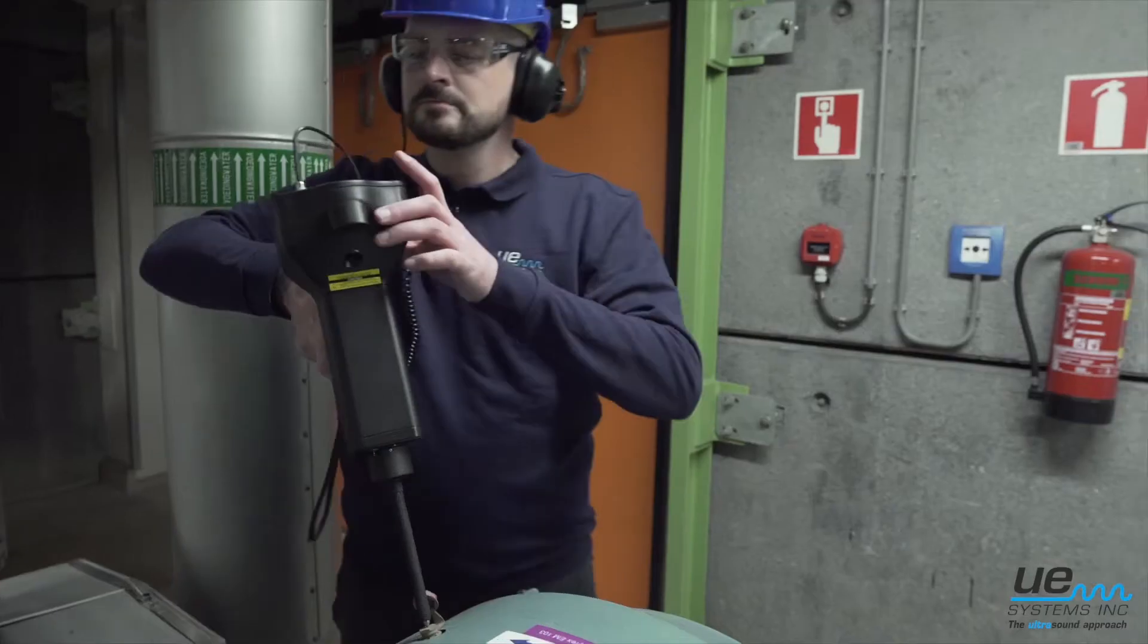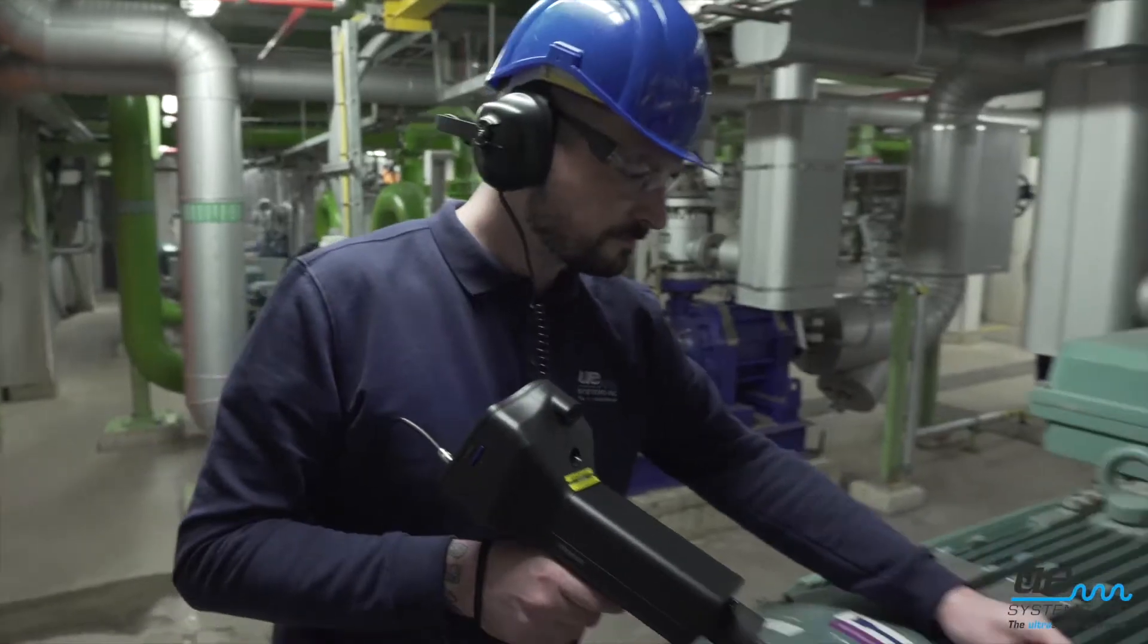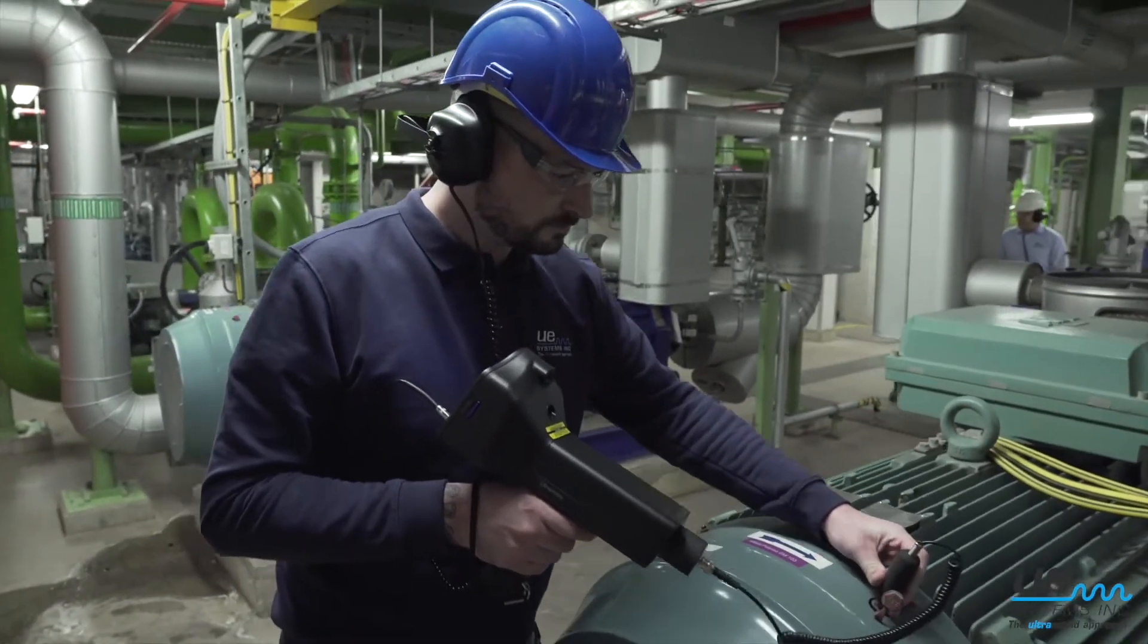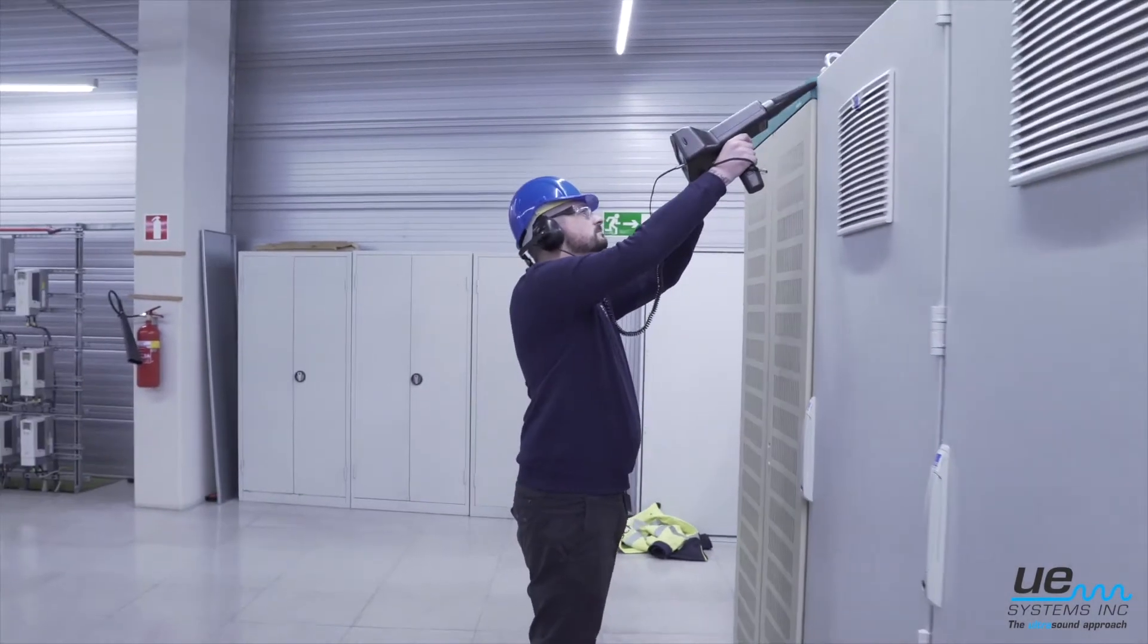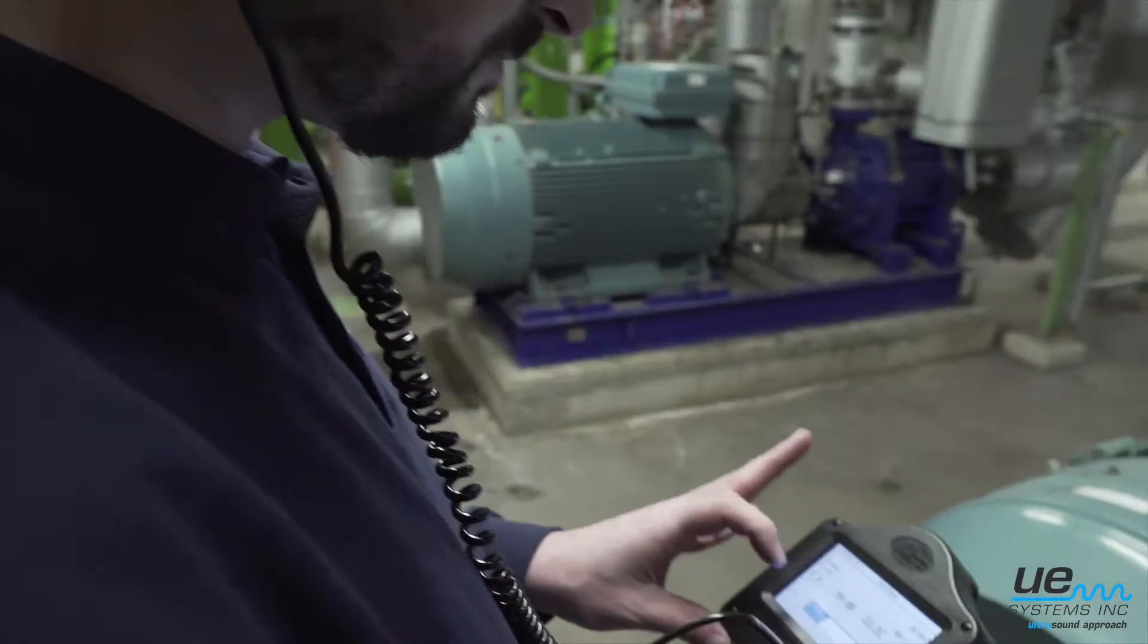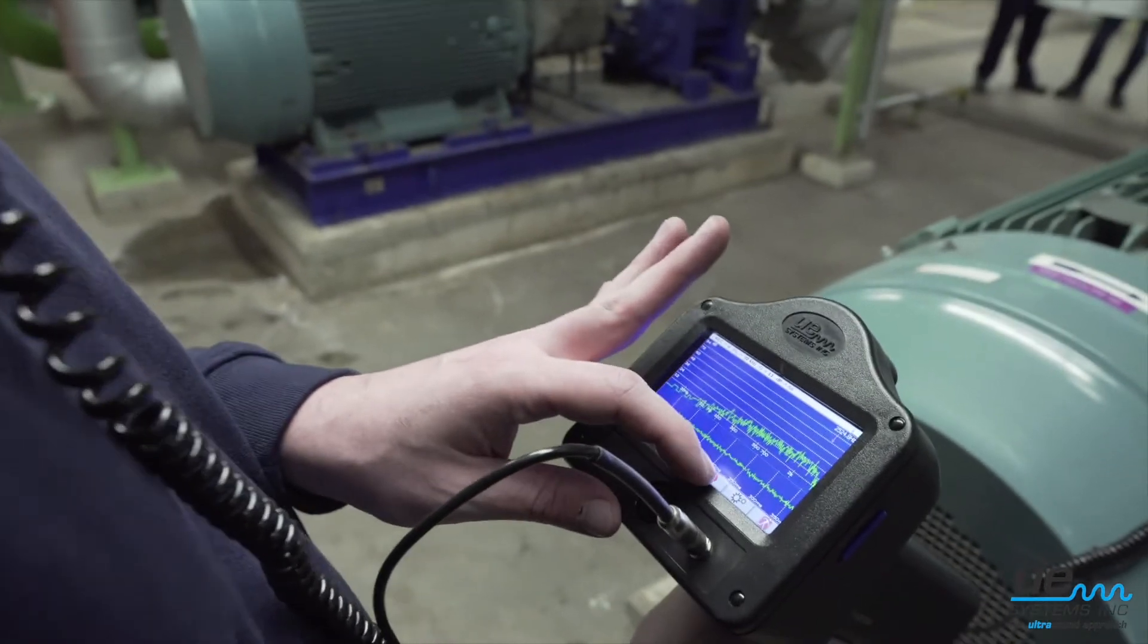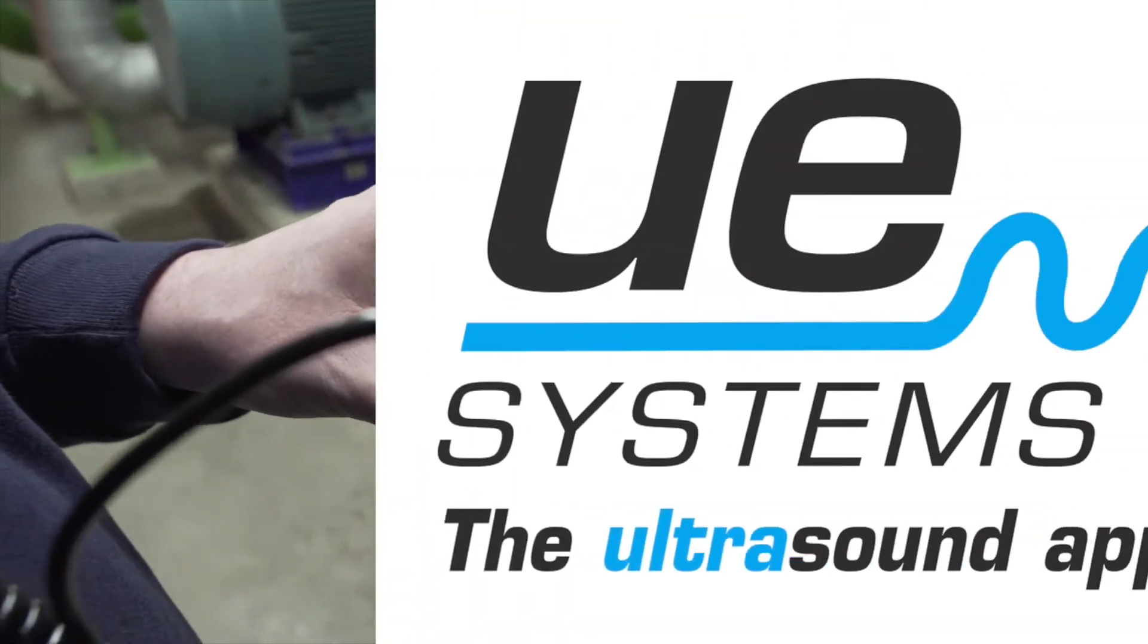When performing ultrasound inspections on electrical or mechanical assets, sometimes it is necessary to use sound recording and analysis for a more accurate diagnostic. Instruments such as the Ultraprobe 10,000 and Ultraprobe 15,000 have sound recording capabilities.